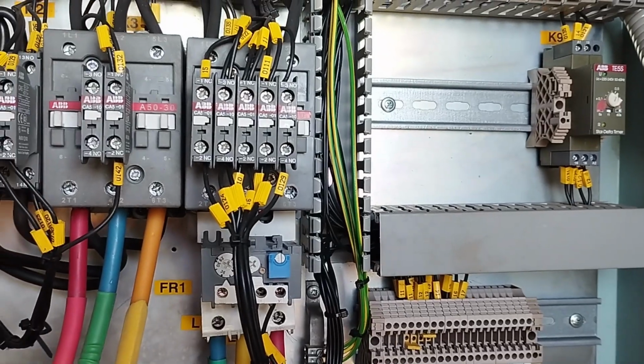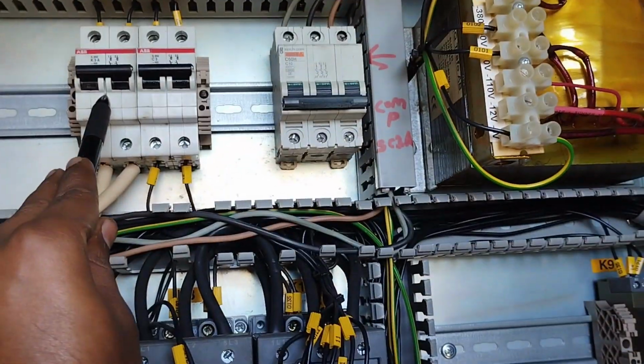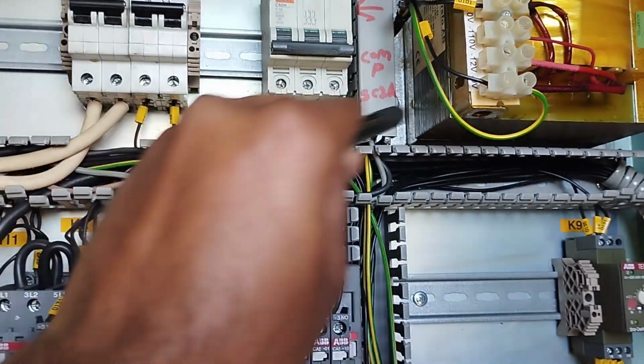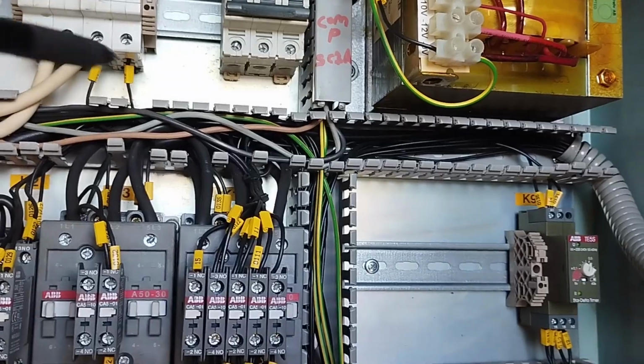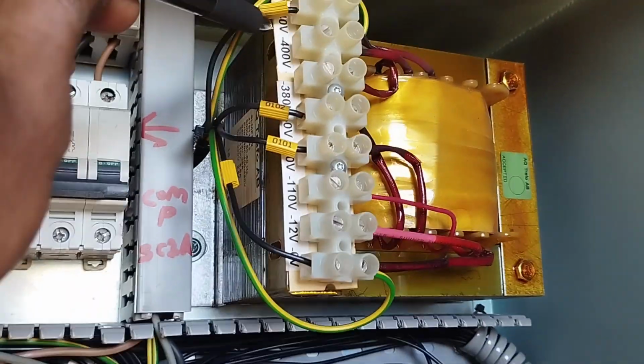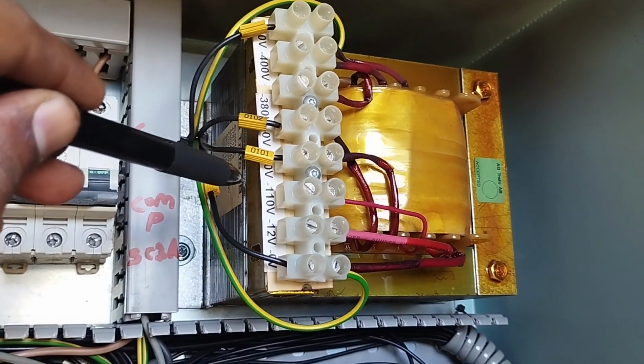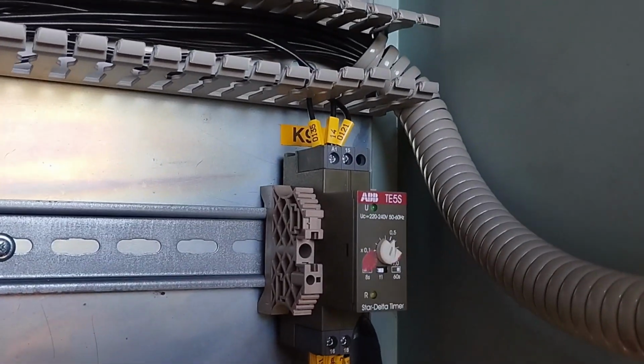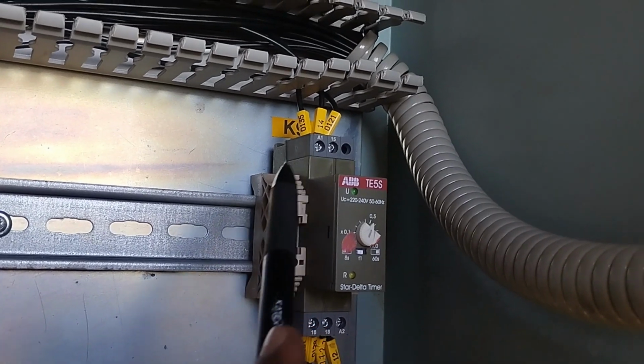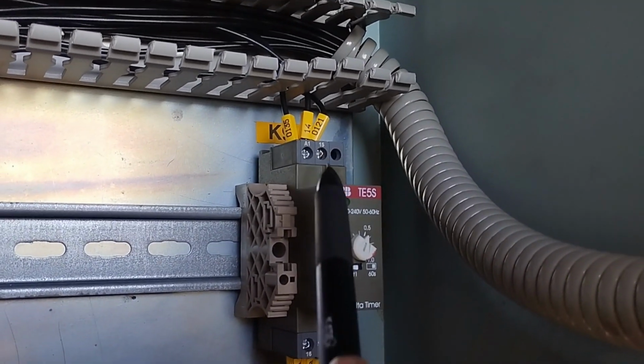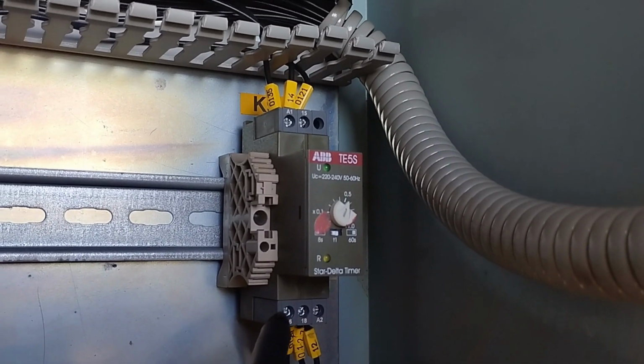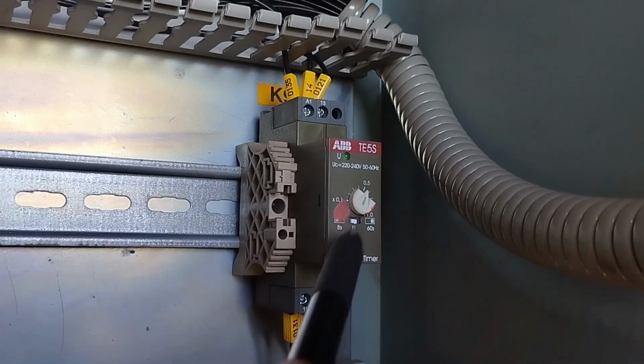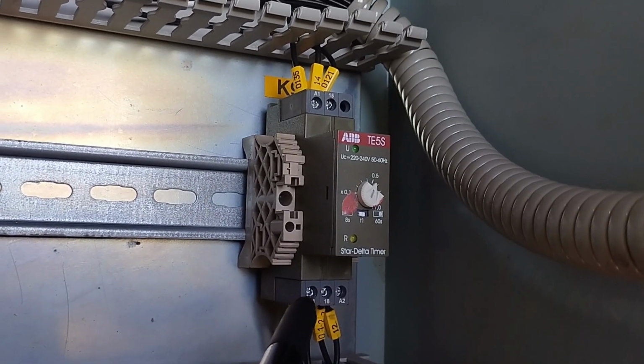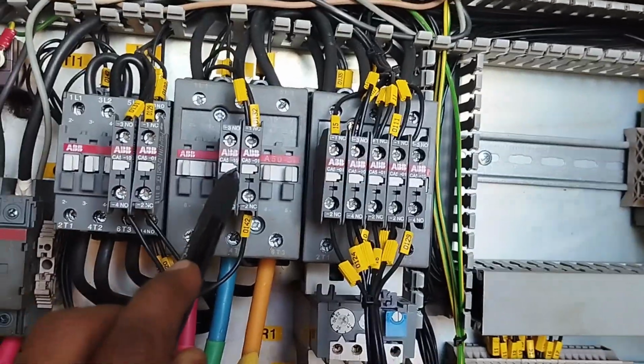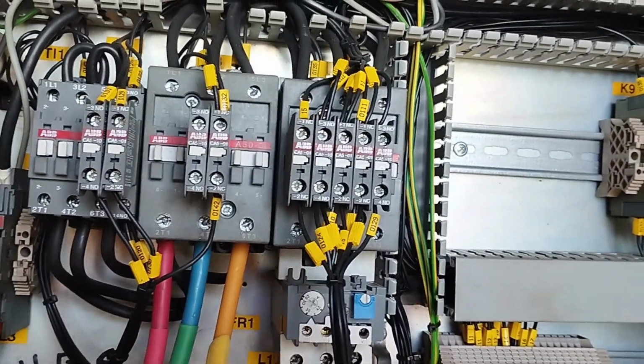because the camera quality is not good. And these are the circuit breakers for the transformer input and transformer output to protect your circuit. This is the transformer, you can see here input 440 volt, and these are the different outputs: 110, 12 volt, 220. Okay, going to the control circuit. And this is the timer. You can see A1 and A2 are the coil terminals, 15 and 16 are normally closed, and after the 5-second timer 15 and 18 will close and 16 will open, and the motor will start on the delta and main contactor at high speed.